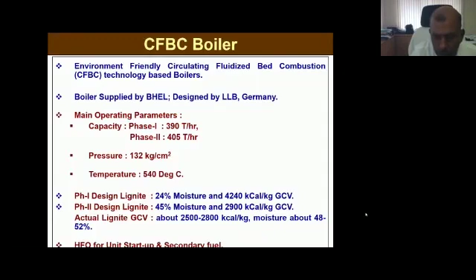Here I would like to discuss and highlight the salient features of the CFBC boiler, which are more on the environmental side. As I have shown in the previous slides, it is suitable for low-grade fuels. The fuel we are using is almost 2,500 to 2,800 GCV. Apart from the low GCV, the major issue is the moisture, which is in the range of 48 to 52%. I mean to say, of the total content of the fuel, 50% is moisture.